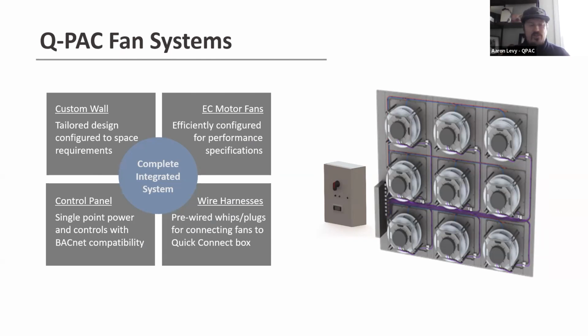versus something like a cube system. Everything's hand carryable. Everything gets through standard size doorways. The heaviest component of the system tends to be the fans, and the maximum weight on those fans tends to be about 100 pounds, 150 pounds at most. We designed the system so that it can be carried through service elevators, hallways, and by 1 or 2 people. The only thing that's not included in our scope is the power and communication conduit between the fan, the main disconnect outside and the quick connect box inside, as we don't know where that controller is going to be mounted. So it's minimal work for an electrician to come to the job site and make those connections for power and communication.